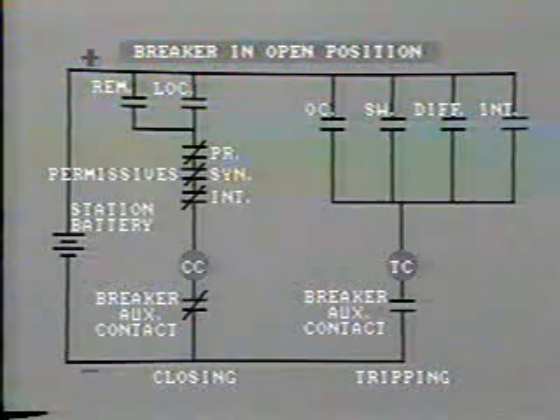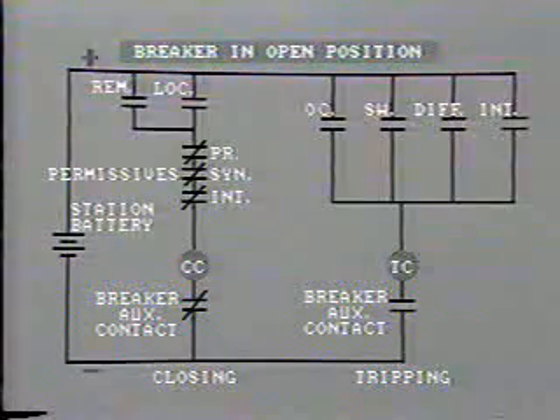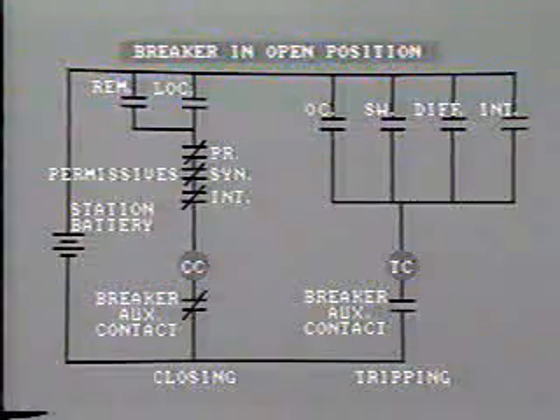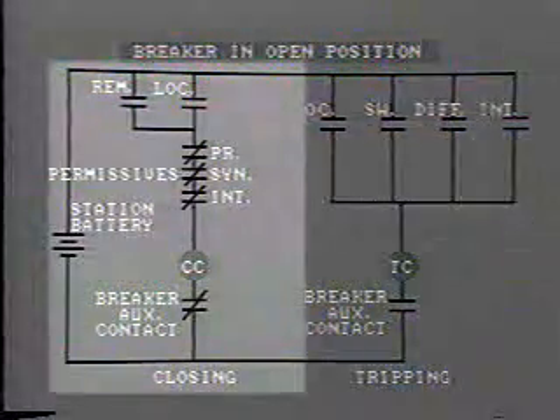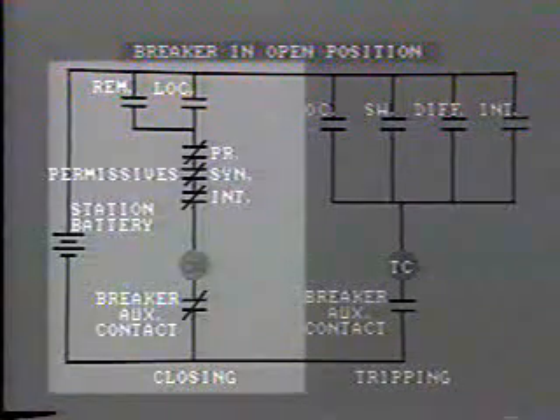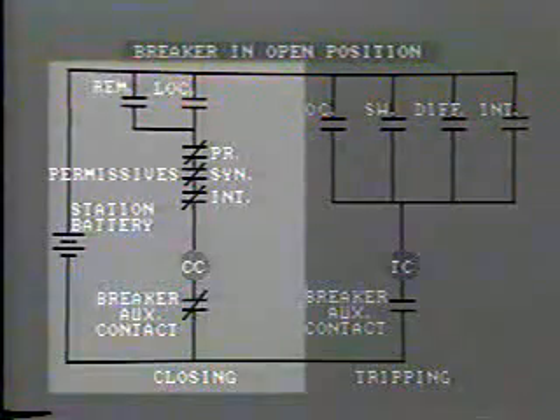The DC, positive and negative, may be drawn horizontally or vertically. It really makes no difference. You soon get used to working through the circuit to determine the sequence of events. Look at the closing circuit of this breaker. To energize the closing coil, the circuit must be completed by closing one or more of these pairs of contacts.